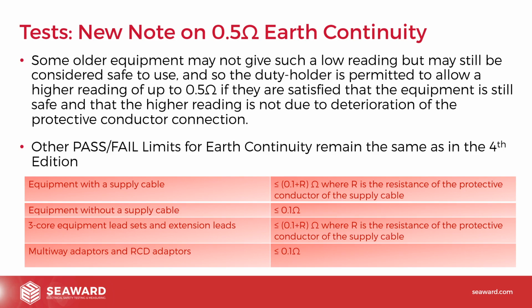Now there's a new note been added on a 0.5 earth continuity pass-fail limit. So just something we need to mention, really. This has been added in as a note. In some of the drafts, you may have seen this in the actual table. In the final published version, it's been taken out of the table and put in as a note.